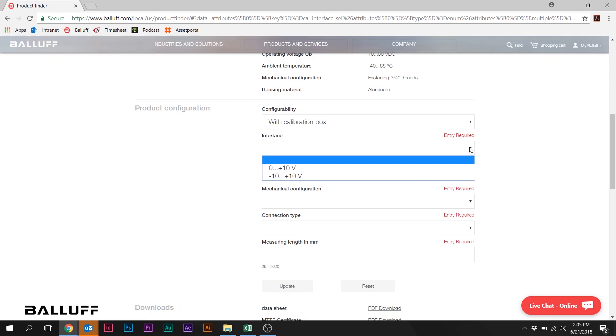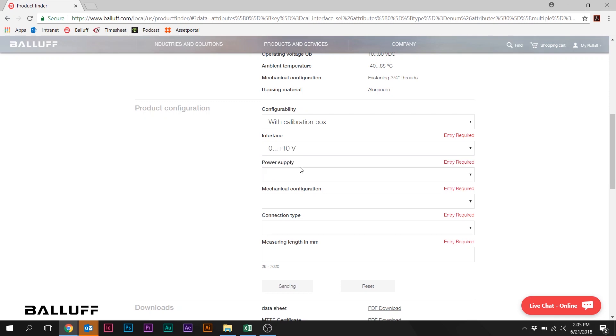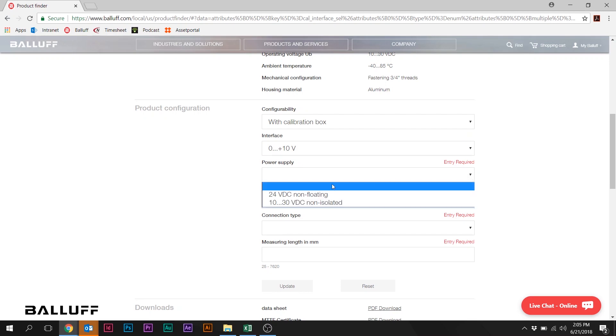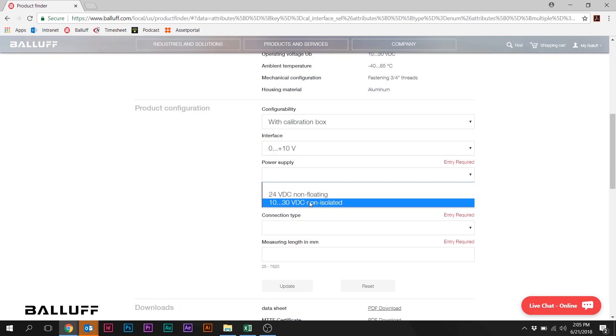Now we're asked to select the interface. We're going to select the very common 0 to 10 volt interface. Next is Power Supply. We're going to select the 10 to 30 volt input power supply version. Again, that being by far the most common configuration.